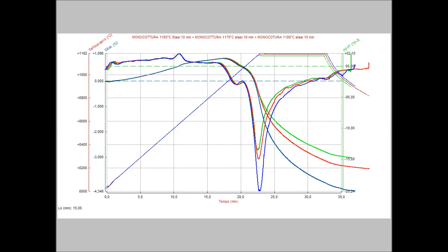The optical dilatometer Misura HT allows the study of the kinetic of sintering as a function of temperature or as a function of time. This graph shows 3 sintering tests at different temperatures, with the first derivative of sintering, or sintering speed, and the heat treatment. A different color is assigned to each test for all the curves: the sintering curve, the speed of sintering, and the temperature. These tests show that the shrinkage increases as the temperature increases, and it grows with time at constant temperature. The derivative of sintering against time, or the sintering speed, is showing that the sintering speed is growing exponentially with temperature, but it decreases exponentially at constant temperature.